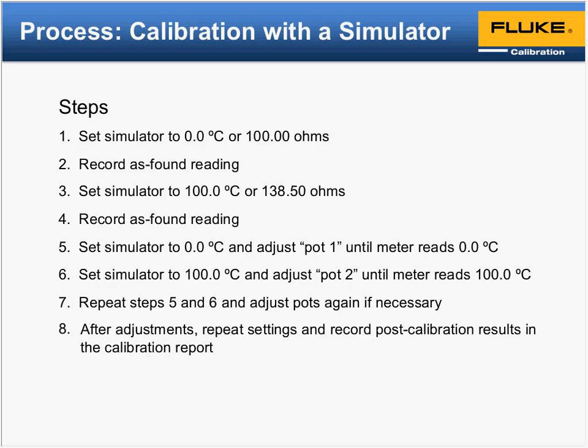So here, as far as calibrating with the simulator, whether you have a thermocouple, an RTD, or you're checking just resistance, basically you're going to disconnect whatever the source is from the readout piece and then connect the simulator. For our example, we're going to near 0 C, which relates to about 100 ohms as far as an RTD. So again, we'll manually record the reading. Next step is to simulate 100 C, and record that data. However, as found data, because this is going to have traceability, if a customer knows the performance, it's kind of key information.